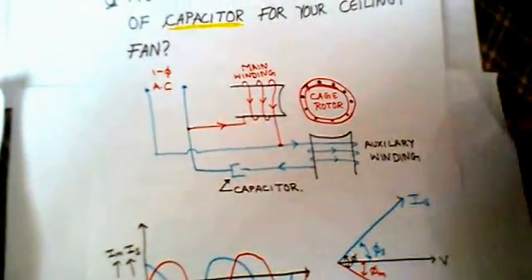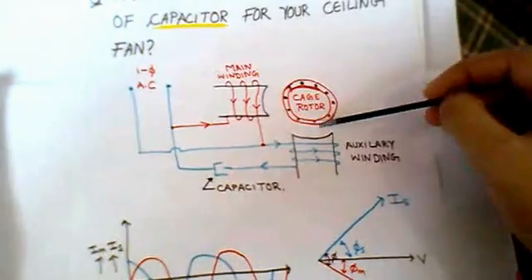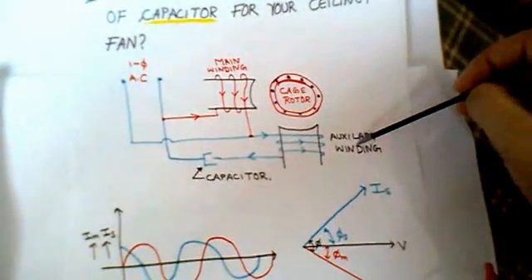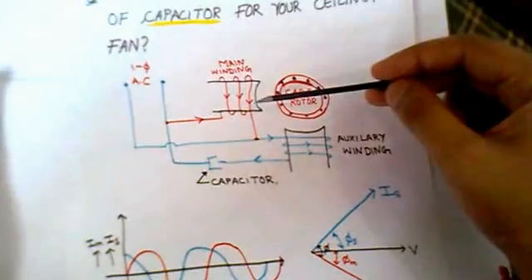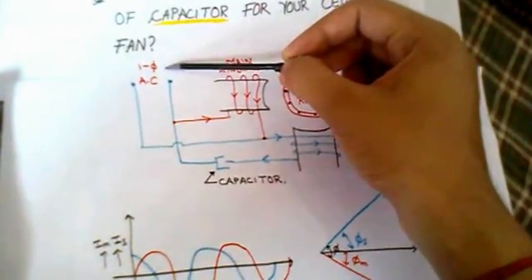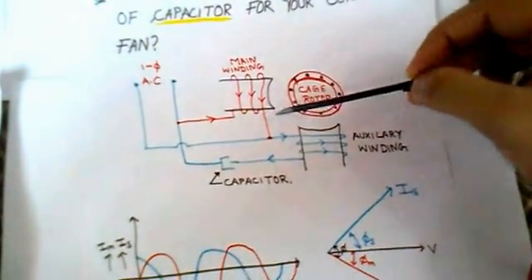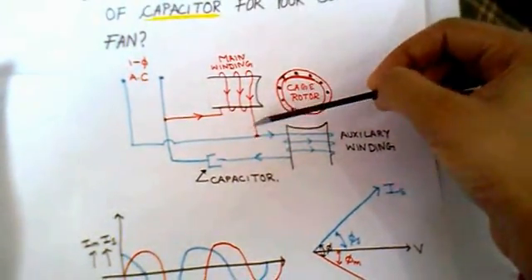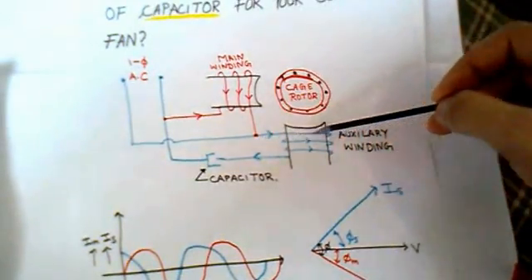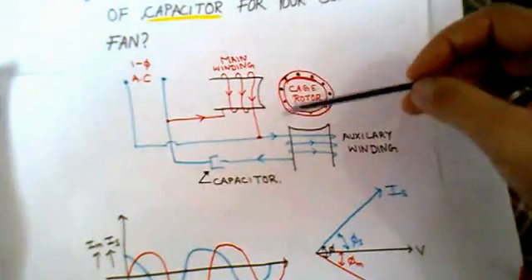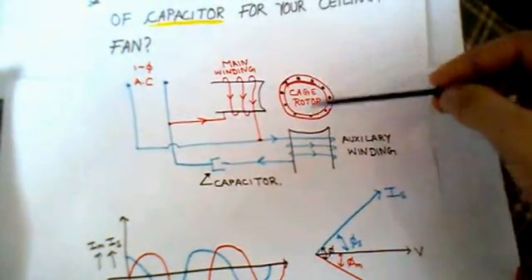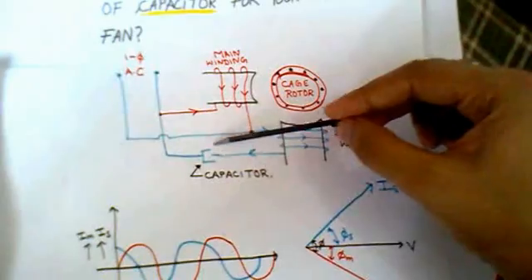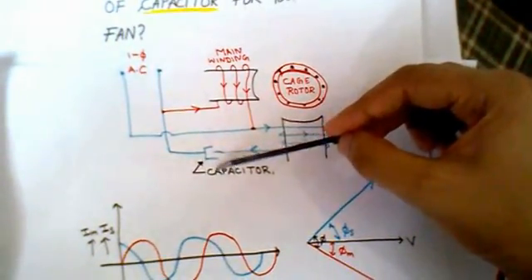To calculate the value of the capacitor, I have drawn a diagram. This is a cage rotor and there are two windings — the first one is the main winding and the second one is the auxiliary winding. We have done two windings to split the phase, that is to convert this single phase AC supply into two phase AC supply. The condition is that the current in the auxiliary winding must be 90 degrees displaced compared to the current in the main winding, and only then we will be able to create a rotating magnetic field which will produce a torque during starting. Here is the capacitor that will be attached, and in this video we will be calculating its value.